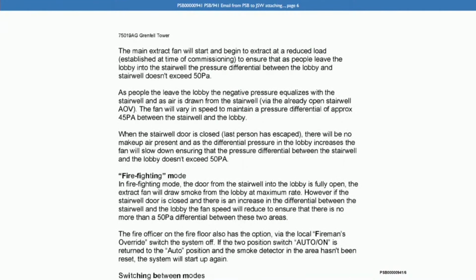Yes, I see. I understand entirely that the 50 Pascal figure is in fact the figure suggested by British Standard 12101 Part 6 and, as you said, by other guidance documents. And I appreciate it says it shouldn't exceed 50 pascals, but why doesn't this method statement record that the design performance criteria was set to achieve a pressure differential of 25 pascals? Can you explain that? Because until I actually set the pressures and the door forces, it could be 50 pascals. It's unlikely, but it could be.